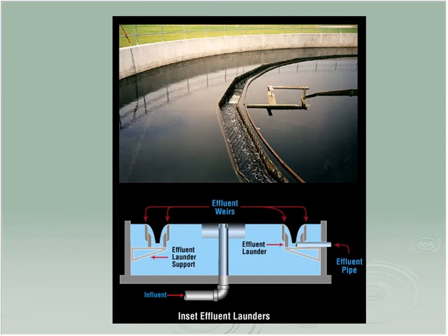Again, the internal launder, instead of having it out at the outer periphery of the tank, the material runs across and hits the wall and comes up. Well, now it's got to turn around and come back about a third of the distance towards the center before it hits that effluent launder. Just another way to hold stuff in longer.